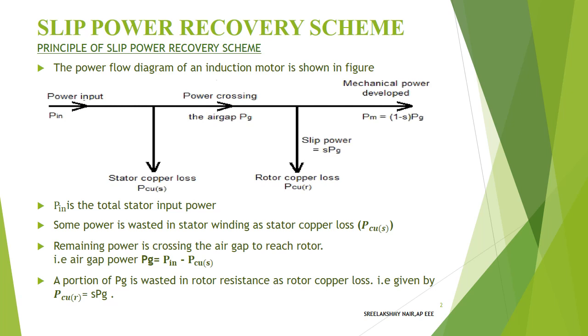After crossing the air gap, mechanical power developed PM is equal to (1 − S)·PG, which is PG minus S·PG. In this power flow diagram: P_in is total stator input power; some power is wasted in stator winding as stator copper loss P_CUS; remaining power crosses the air gap to reach the rotor — that is, air gap power PG equals P_input minus P_copper_loss. A portion of PG is wasted in rotor resistance as rotor copper loss, given by P_CU_rotor = S·PG.